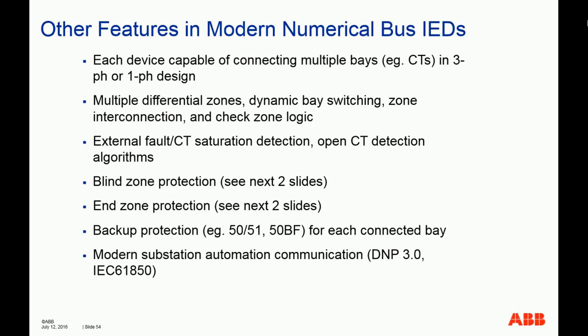Zone interconnection. Sometimes, for example, for the double bus single breaker scheme, if you close the tie breaker or close any of the two breaker disconnect switches at the same time, you effectively interconnect the two buses. So in that case, you want to make sure now all the CTs are connected to the same zone. So you need to have different logic for zone interconnection. And also check zone. Check zone is to make sure you can further supervise the security of your bus bar protection by using the check zone to supervise the operation of the differential protection.